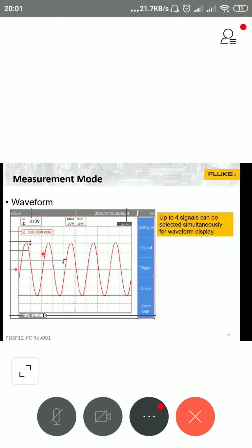And as I mentioned, this has a wide bandwidth, from 0 to 500 kilohertz. Here you can look at the waveform, a sinusoidal waveform, or if it is a pulse width modulated signal, the motor output, the VFD output. Yes, you can still measure the pulse width modulated signal simultaneously on four voltage as well as current channels.